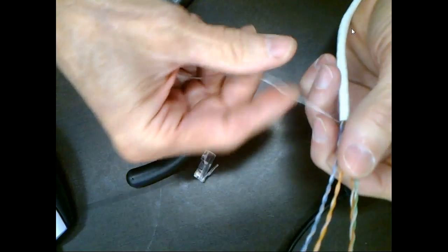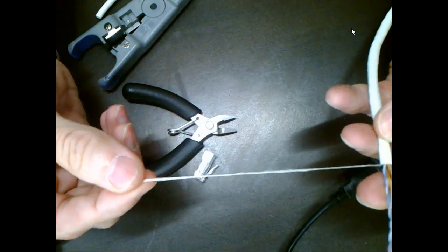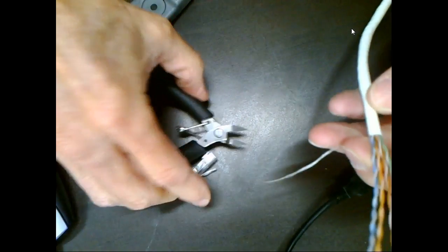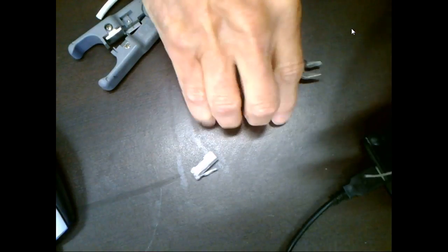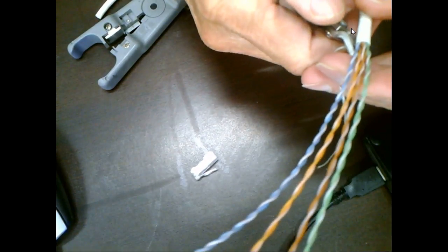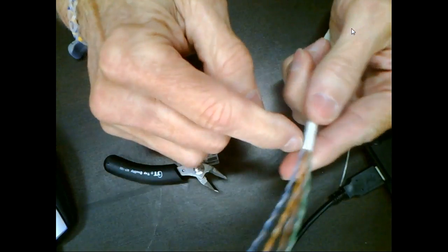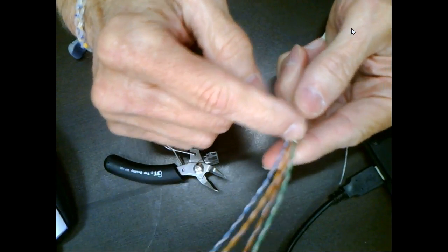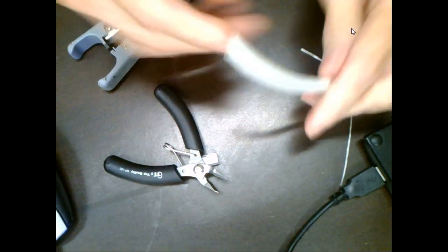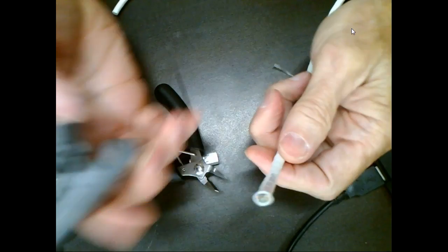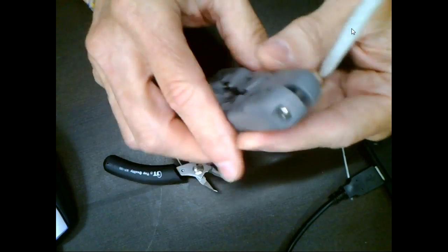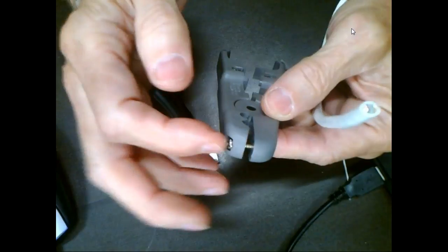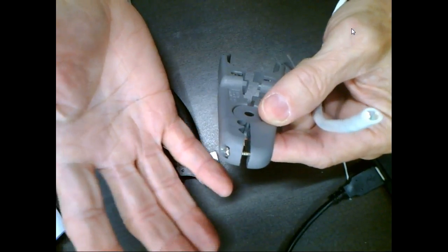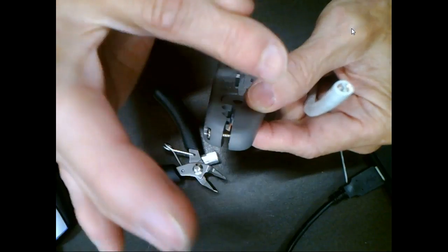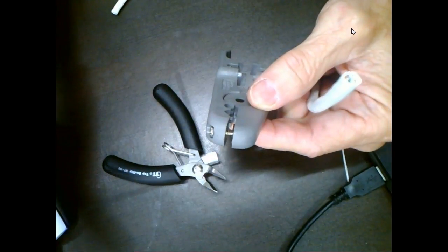Yeah. So what we have inside the cable is a strength member that we'll need to cut out. And when we strip the wire, we want to make sure we don't scribe the wire at all. You know what scribing means, right? Okay. So we have special cable strippers that you'll use. You don't want to use a pocket knife to do this. And you need to check it before you actually do stripping, because if it scribes the wire, which means cuts the insulation, then you're going to have to clip it off and start over.